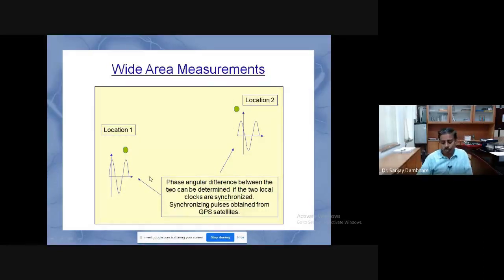But for differential protection of a transmission line, we are interested in the phase as well as the magnitude difference — the phasor difference. These two signals are measured with the same time tag, and this time tag is taken from the GPS, which is common to both locations.